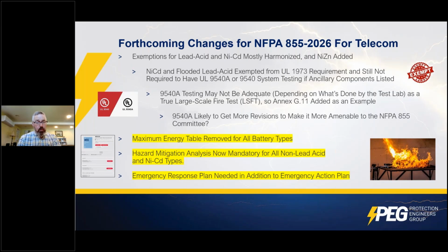Every installation has needed, for the last couple editions, an emergency action plan. That basically says if I have an energy storage system, a UPS, somewhere at a facility, if there is a fire, people know how to evacuate, get out. That's a general OSHA requirement for a workplace. Now, everyone also needs an emergency response plan. That's basically a document that tells the firefighters how to respond and address an emergency.